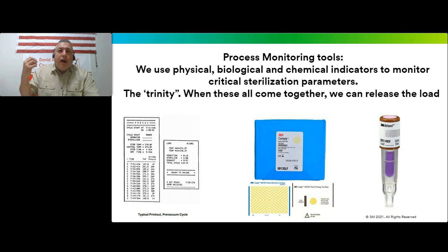I'm saying this because in my past, I was in a department when I was a technician, and the sterilizer repairman had come in and was running some tests on the sterilizer and changed the exposure settings. I believe at the time, the newer models sometimes won't let you go below 4 minutes, but back in the day, we were able to turn that exposure time to zero. He was doing some kind of testing and never changed it back. Two cycles were run, and of course all the parameters on the printout said yes, yes, yes, because the machine was programmed with zero exposure.